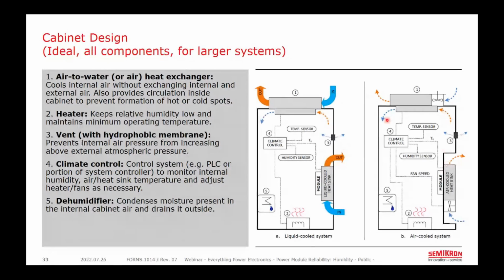In this air-cooled system on the right, you can see that we've separated the airflow over the heatsink from the internal airflow. And though it's not touched upon in this presentation, one of the biggest issues with air-cooled cabinets is drawing in pollution, dust and debris into the cabinet along with the cooling air. And of course, it also would draw humid air into the system. And this design here keeps the pollution away from the components inside the cabinet, though ideally we would want some filters for the heatsink air as well.